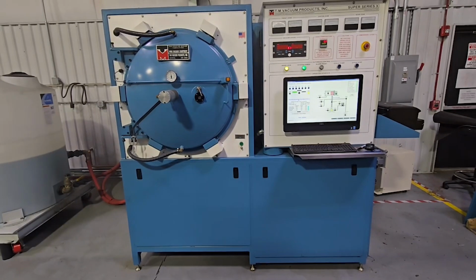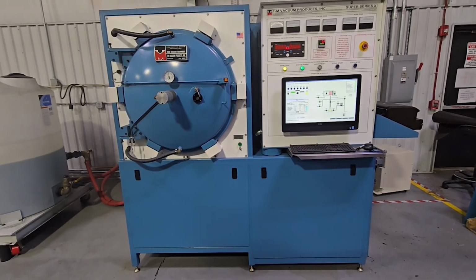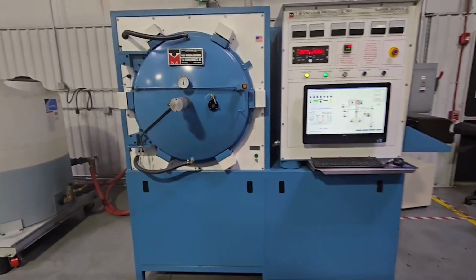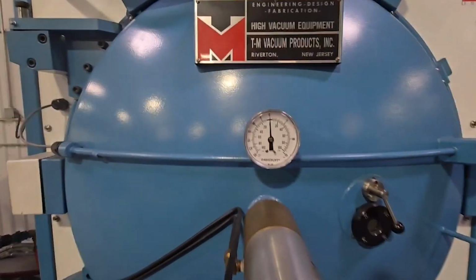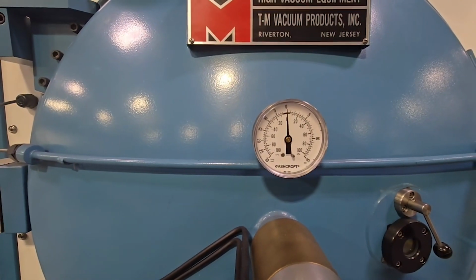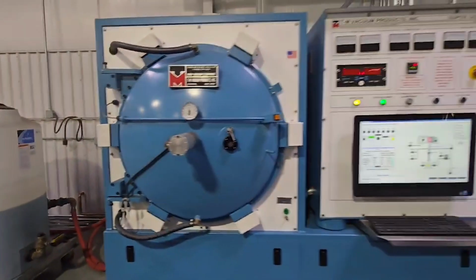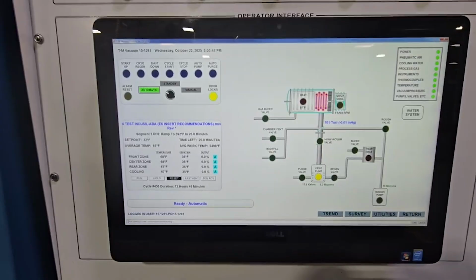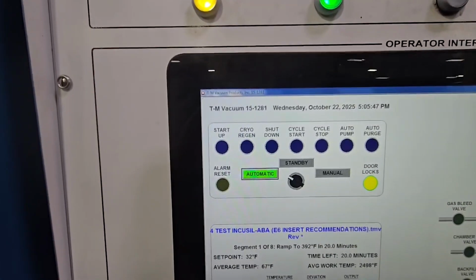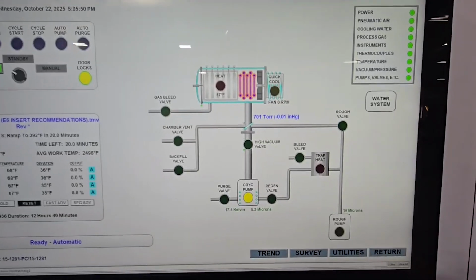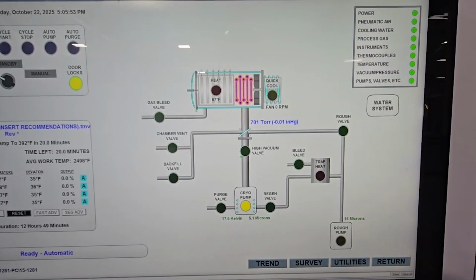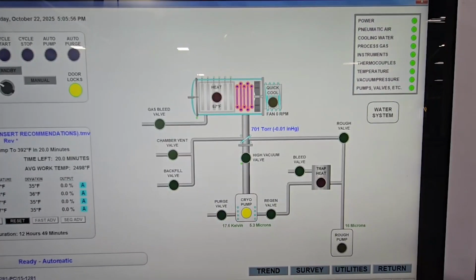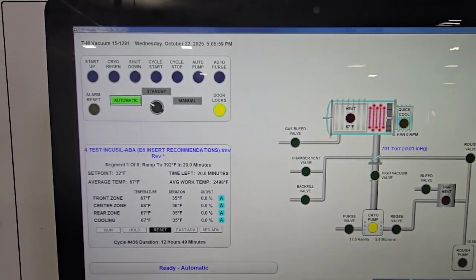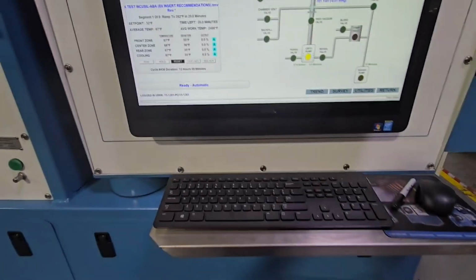The TM Vacuum Super Series X vacuum brazing unit. You can see the chambers on the left side. That's your torr reading, that's reading within the chamber. You have your control side with a very simplified touchscreen. You can run in a manual mode. That way you can control each aspect of the chamber, whether it be rough pump, cryo pump, heating, all your valves, the vent, exterior. It's all touchscreen. There is a keyboard in front with a mouse that you can also use as well.